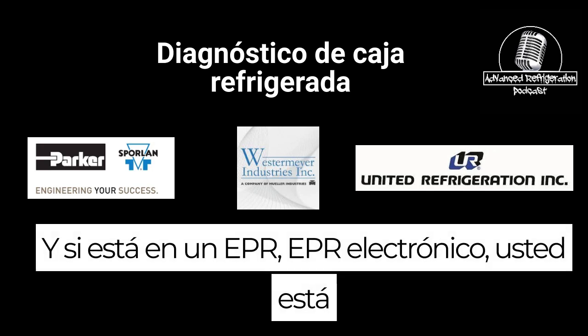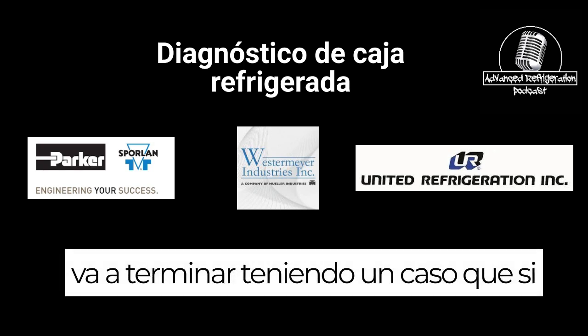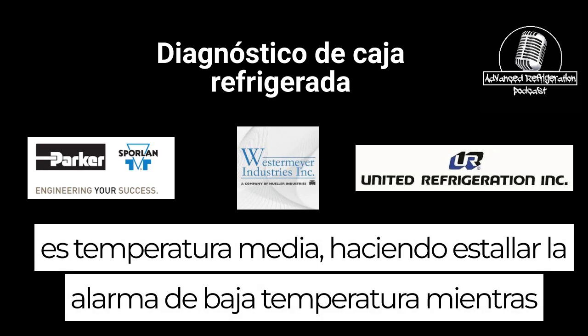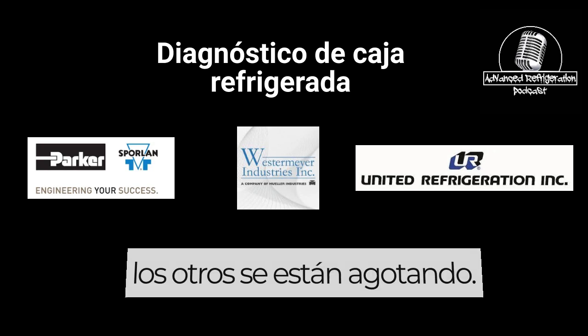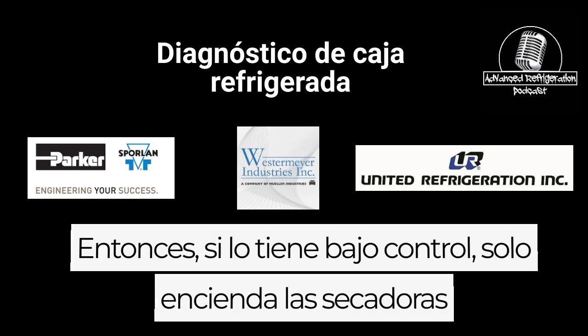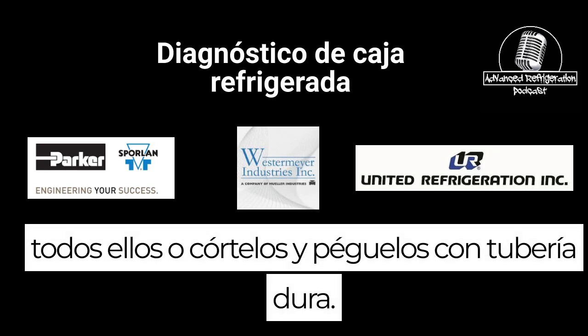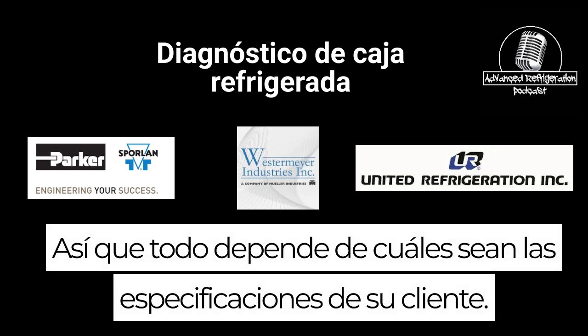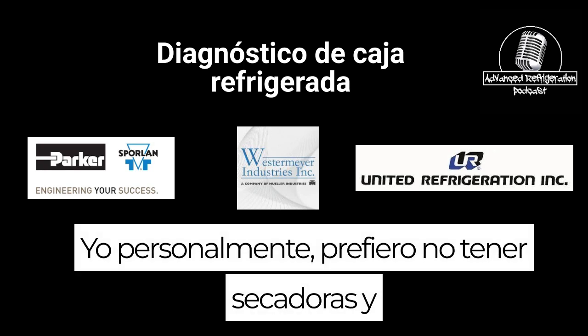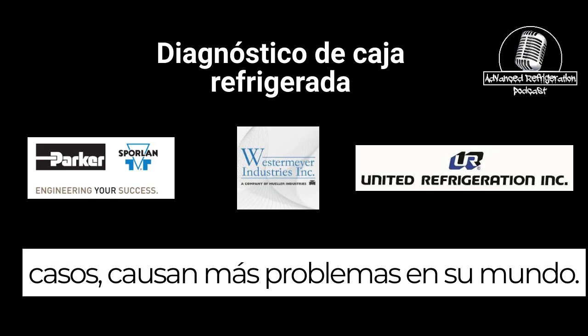And if it's on an EPR or electronic EPR, you're going to end up having one case with its medium temp popping the low temperature alarm while the other ones are running high. So if you got it down, just do the dryers on all of them, or cut them out and hard pipe them. It all depends on what your customer spec is. Me personally, I'd rather not have dryers in cases. I think they cause more problems than they're worth.